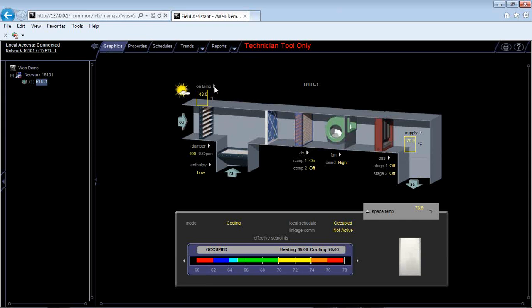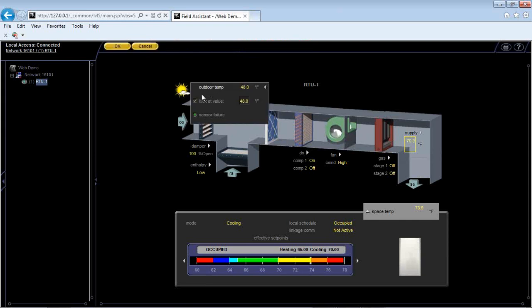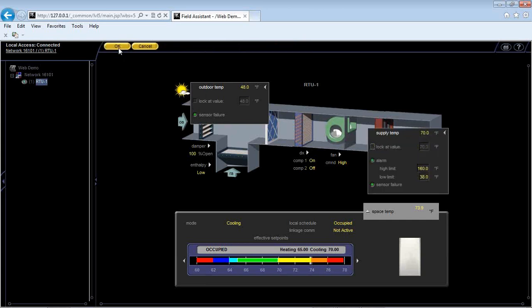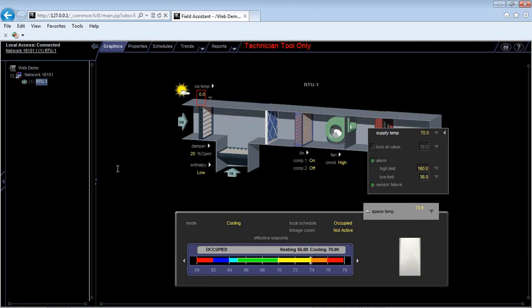Okay, so what you always want to do if you're faking stuff out is always unlock it, because if you lock a value on here, it's going to stay there until it's changed, right? So you do not want to be leaving these values locked, or else you're going to run into issues where the unit's not going to run.